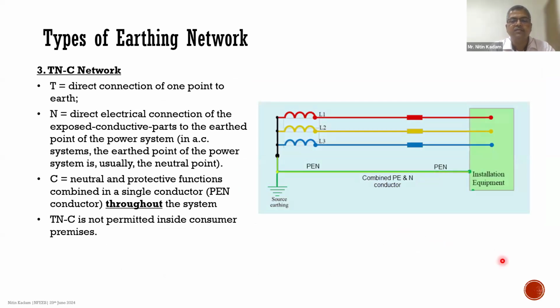Going to the next network type, it is a TNC network. If you see here, there are only 4 conductors coming from the power supply transformer or the distribution transformer to the building installation. You have the 3 phases, and you have a common PEN conductor, that is a common protective earth and neutral, coming to the installation. Now, this kind of network system is not permitted to be used inside the consumer premises. Why? Because if there is a breakage of this PEN conductor, then the installation or the equipment supplied through a TNC network will get charged in case of earth faults, and it will provide a shock hazard to the person touching this conductive part and the extraneous conductive parts in the building. So this is not supposed to be used.